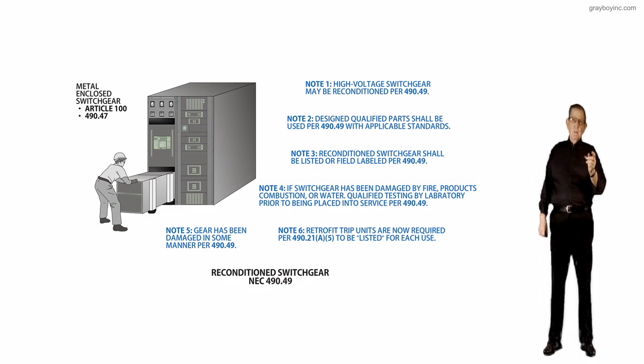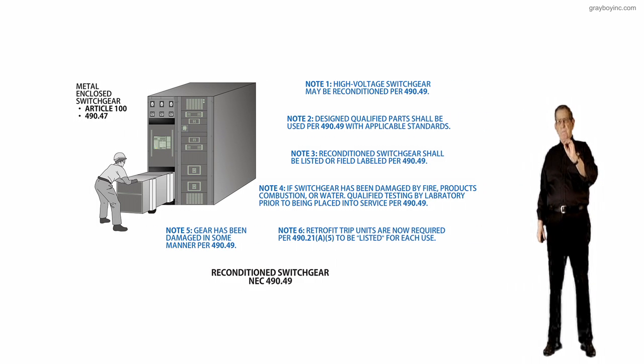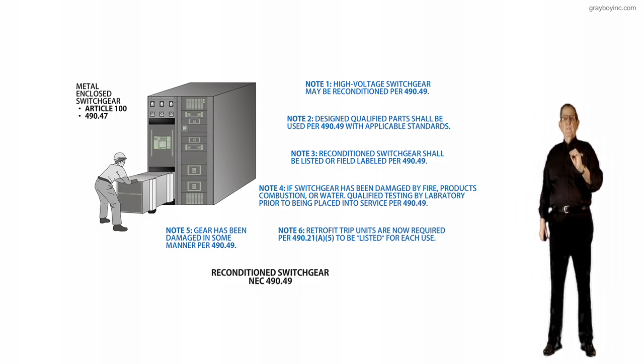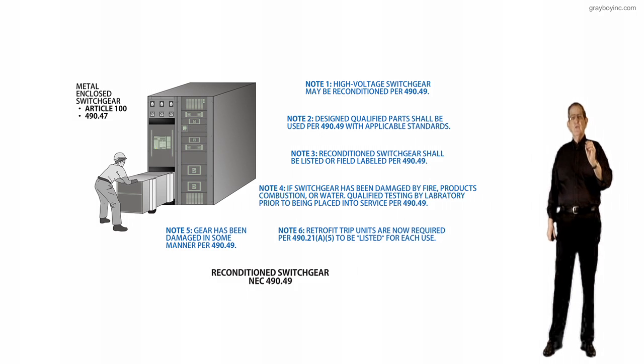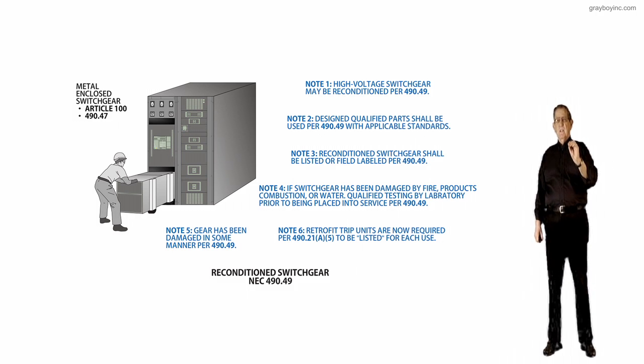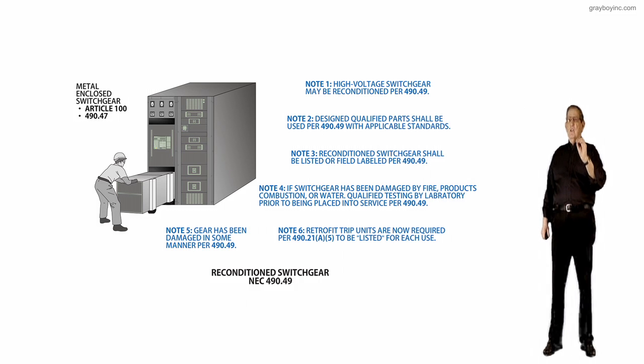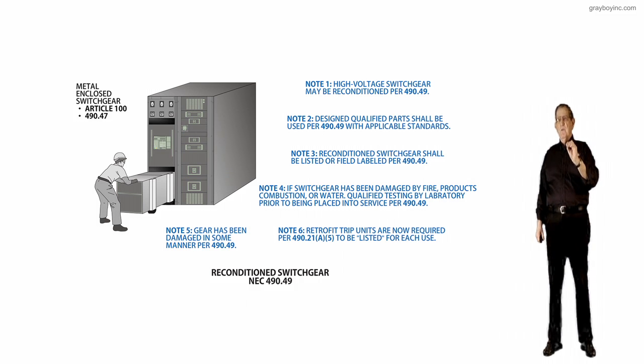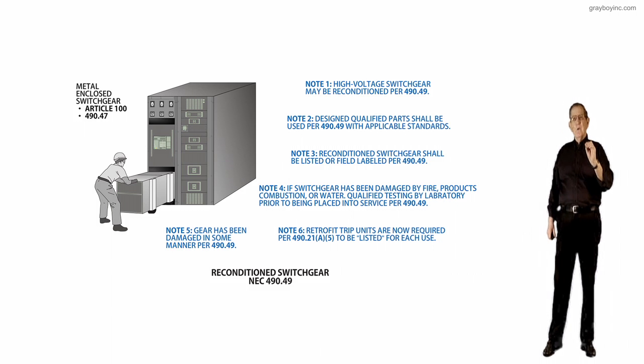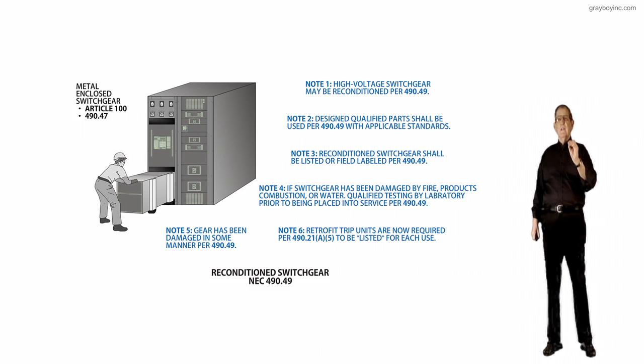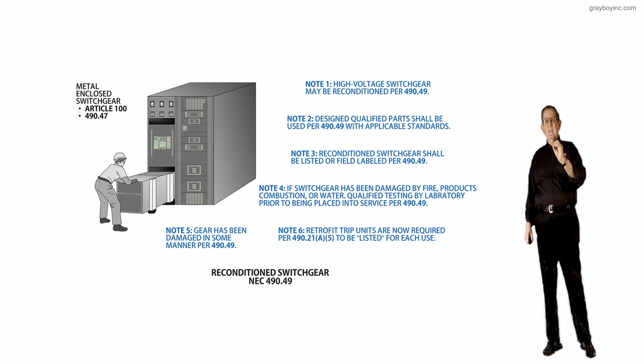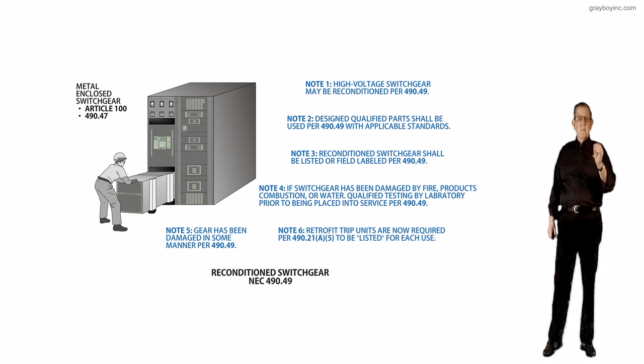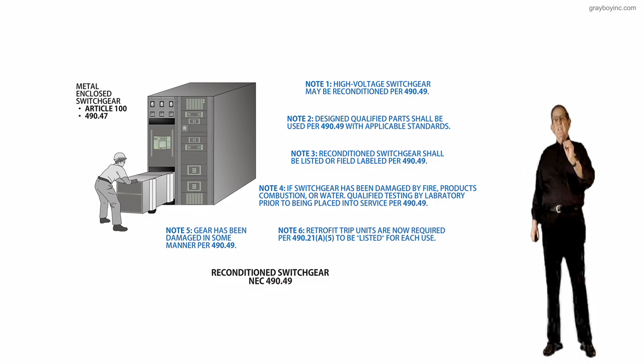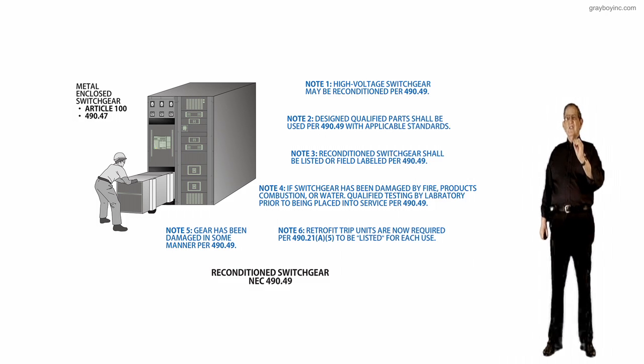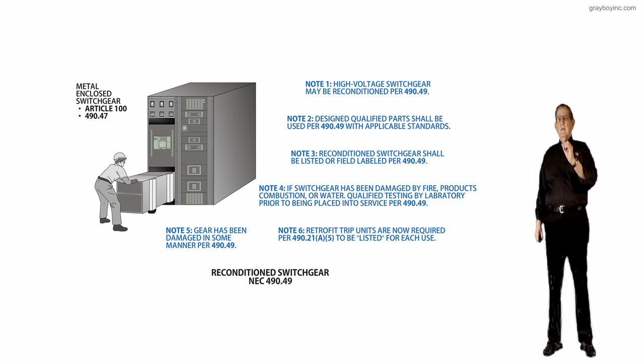This illustration deals with reconditioned switchgear in accordance with 490.49. The purpose of the change was to accept a new section. And this new section has been added to clarify that switchgear can be reconditioned, and typically that work is done in place due to the inherent construction difficulties and expense in removing and installing, say, a new one. In such cases, the best approach is assuring safety before restoring to service.